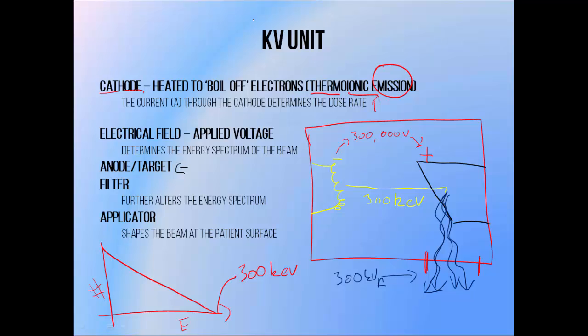If we want to alter the energy of the photon beam, we can change the voltage, since this will change the maximum photon energy of the beam, but we normally do this in conjunction with beam filtration. We do this by passing the beam through a square of metal, usually aluminium or copper, positioned below the beam exit window. This removes lower energy components of the beam spectrum, increasing the average energy slightly, which is useful for treating anything that isn't the actual surface of the skin.